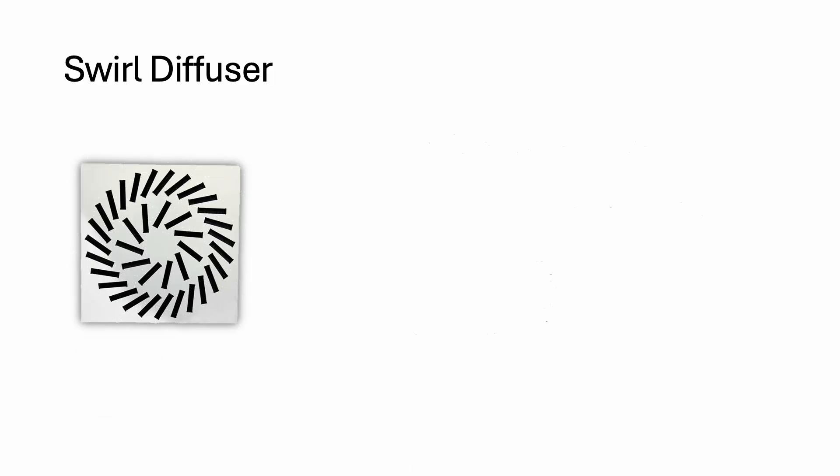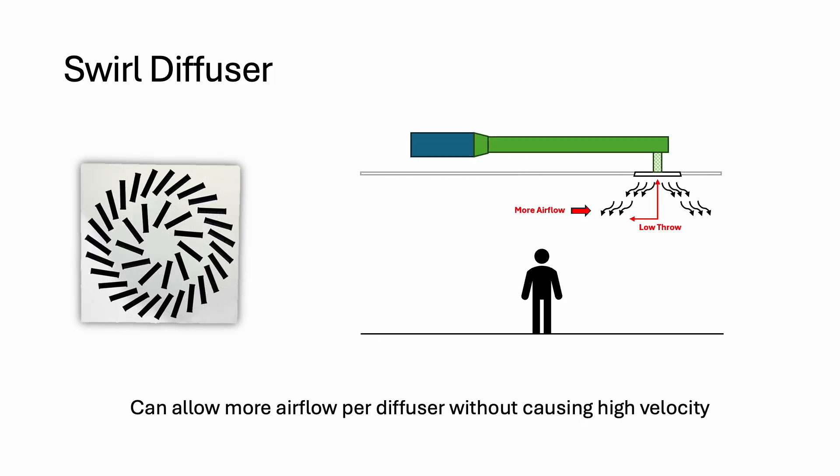As for this type of diffuser, it is known as a swirl diffuser. Its throw distance is shorter than a directional diffuser. This means we can allow more airflow per diffuser while ensuring the air reaches terminal velocity before entering the breathing zone.